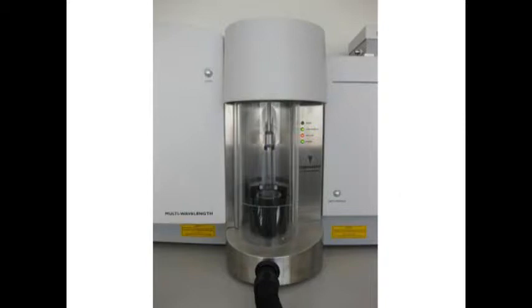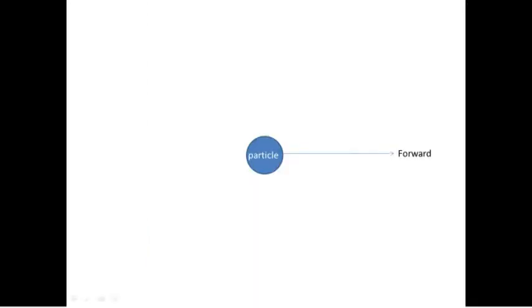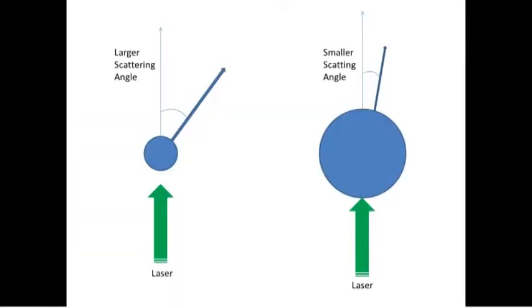It can handle dry powder samples in the 0.4 micron to 2000 micron range. It uses single wavelength diffraction method to find the particle size measurements. The setup consists of high intensity monochromatic light and photodiodes to detect and record angle and intensity of scattered light. The light from the laser light source illuminates the sample and scatters the light signal. The signal is then detected by the detector, and the system vacuums the powder and disperses cohesive powders without milling the fragile portions. Larger particles scatter intensely at narrow angles, while smaller particles scatter weakly at wide angles.